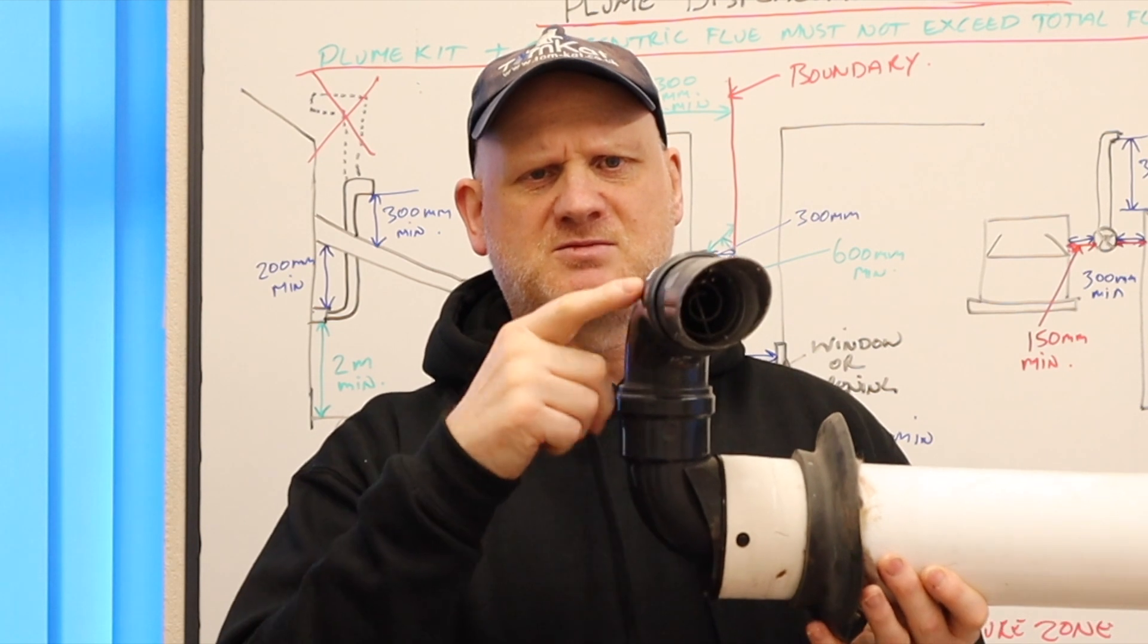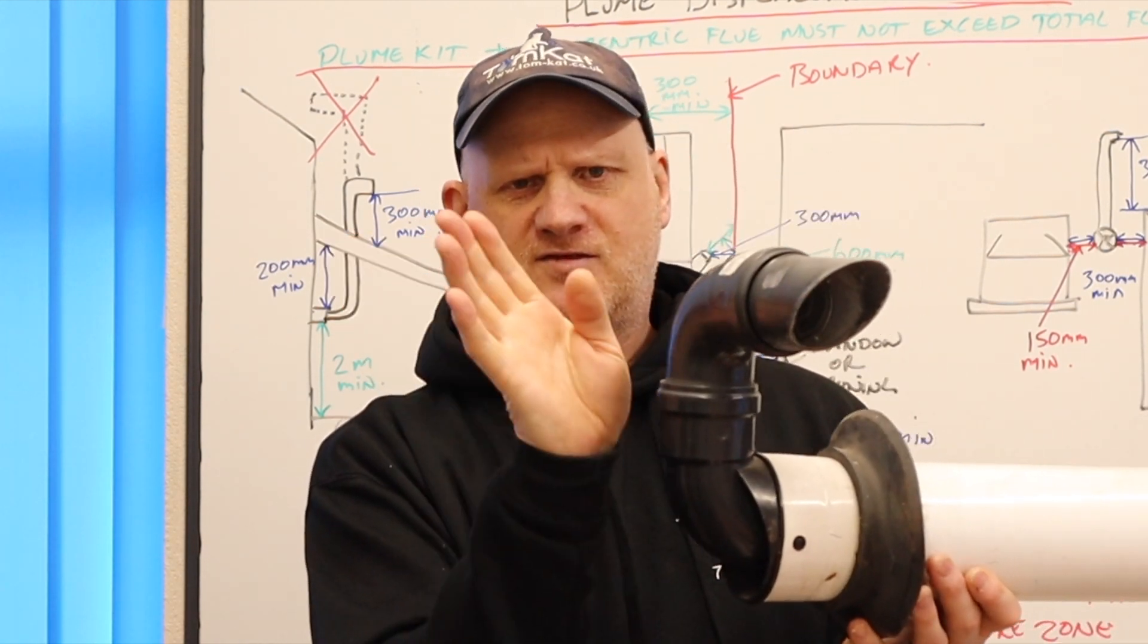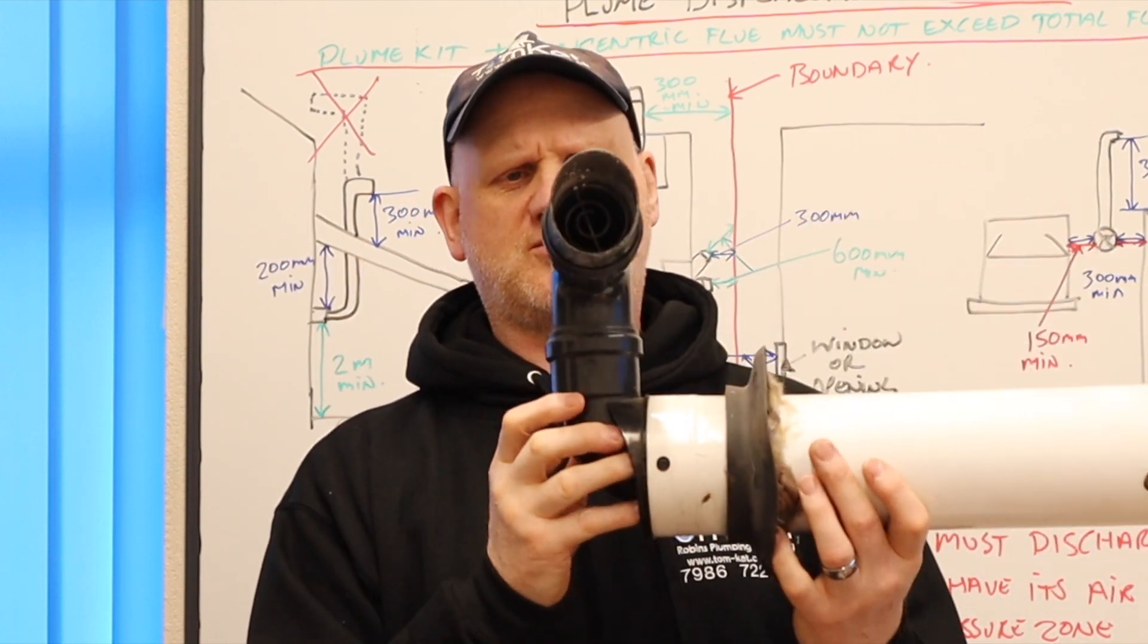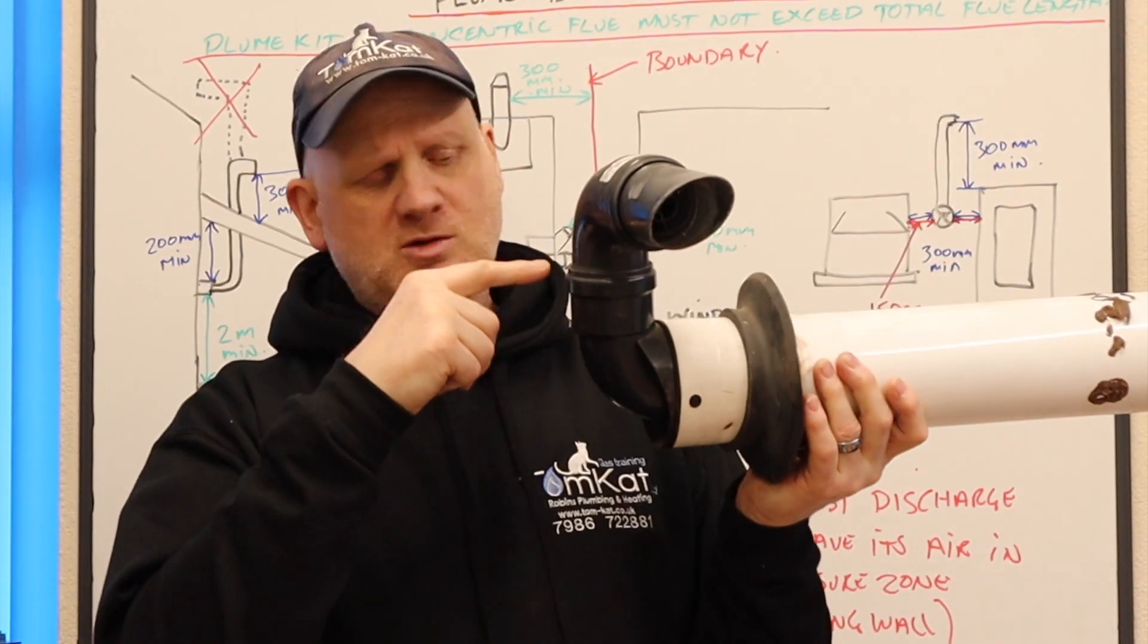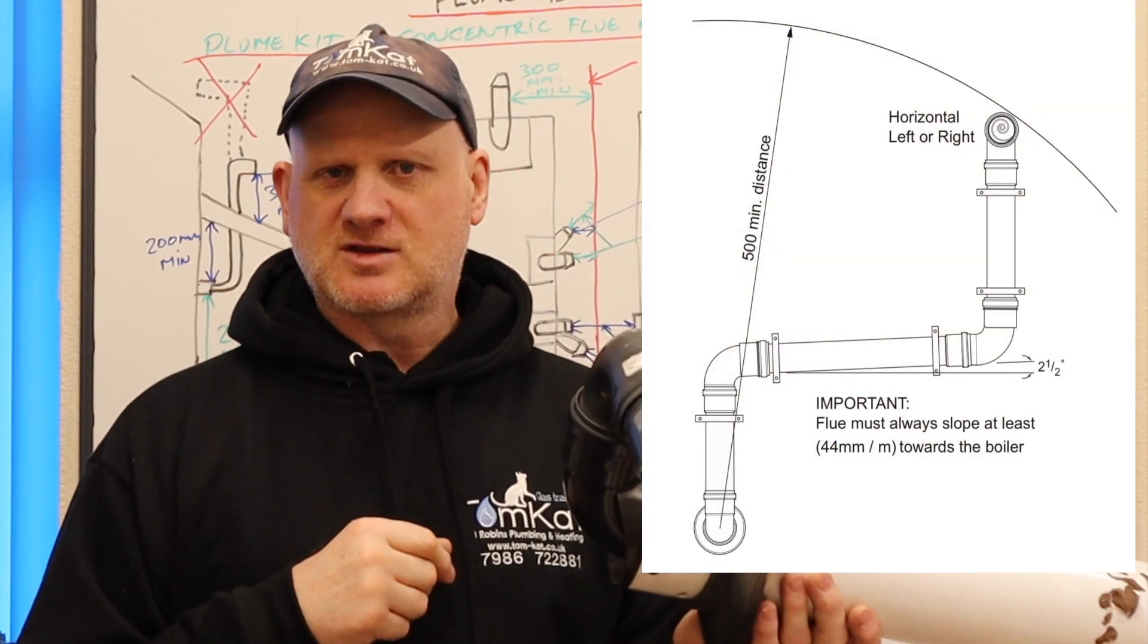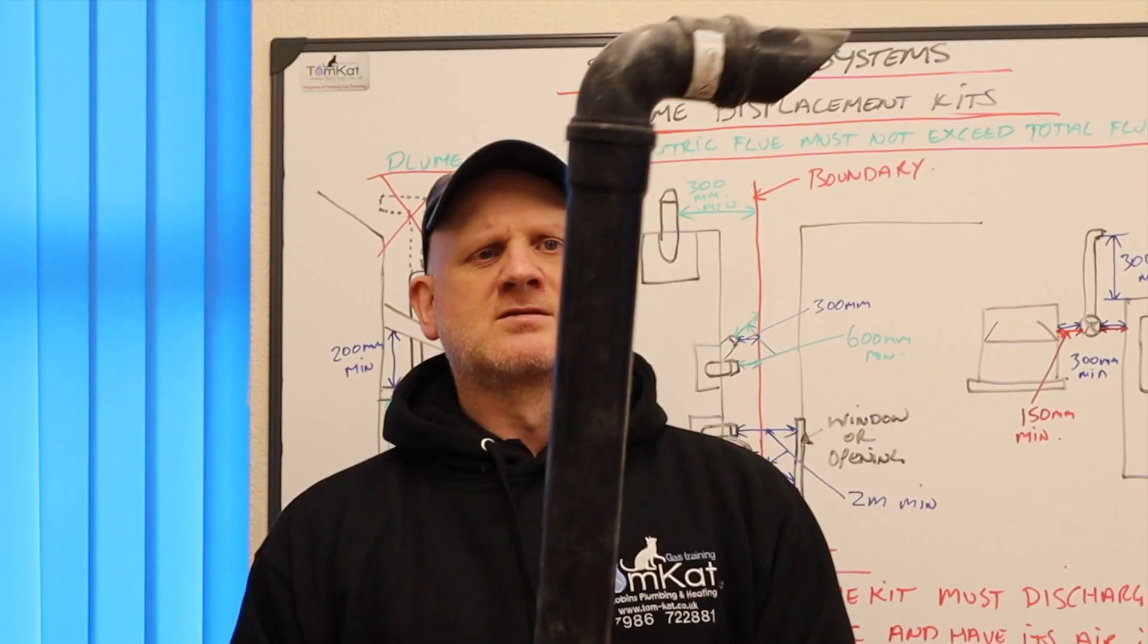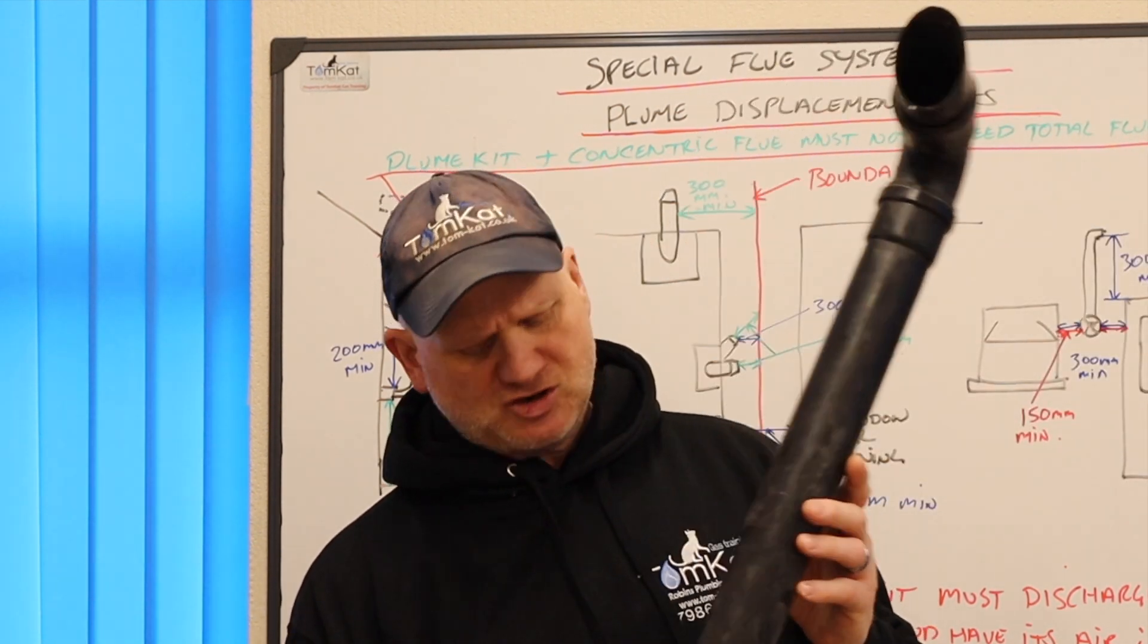The only problem is the maximum angle you can put for this is 45 degrees from 90. So that would be actually installed wrong, but it doesn't spin anymore. Also, we can't just come off the top like that because we have to have a minimum height in a flue system using a plume management kit of 500 millimetres. So we use these extension pieces.